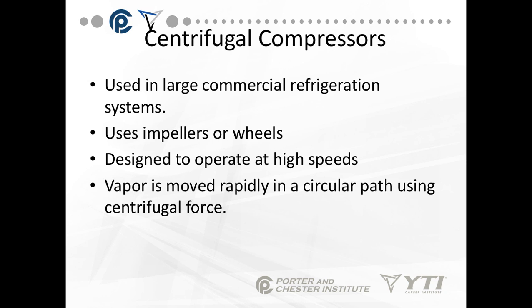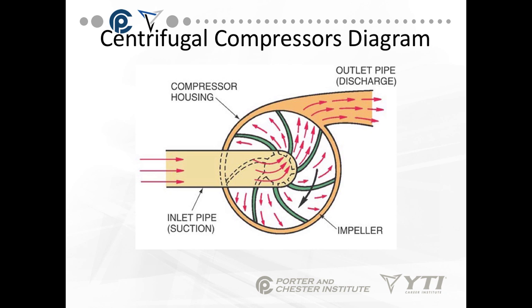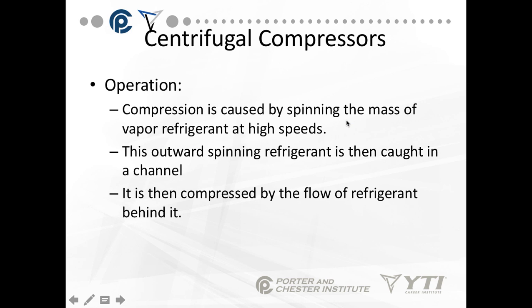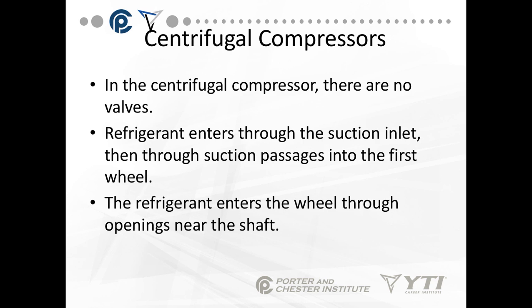Vapors move very rapidly in a circular pattern using centrifugal force. We pull vapor in on the suction line, and as the impeller spins in the compressor housing, it's going to increase the pressure and push it out the outlet pipe or discharge. The compression is caused by spinning the mass of vapor refrigerant at high speeds. The outward-spinning refrigerant is then caught in a channel and compressed by the constant flow of refrigerant behind it.